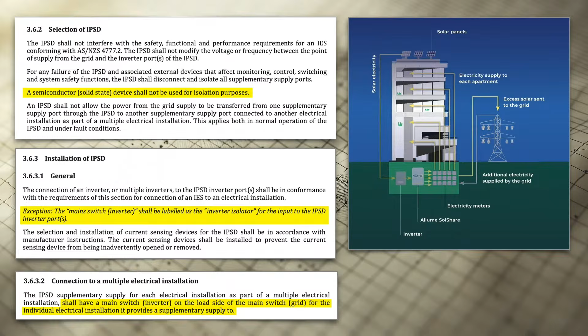There's an exception for the main switch inverter. It shall be labelled inverter isolator for the input to the IPSD. And for connection of multiple electrical installations, you shall have a main switch inverter on the load side of the main switch grid for individual electrical installations. So basically, in each apartment, you will have a main switch grid, a main switch inverter, and that inverter supply is coming from the IPSD. So those are some of those requirements. It does take a little bit to get your head around.